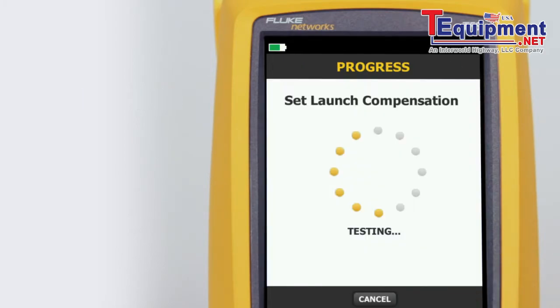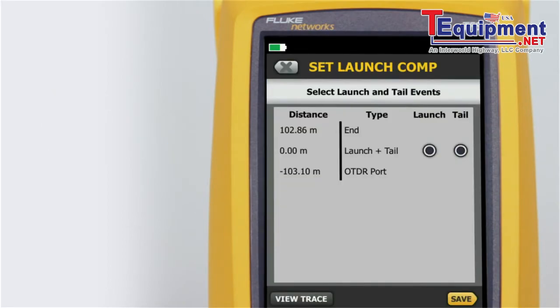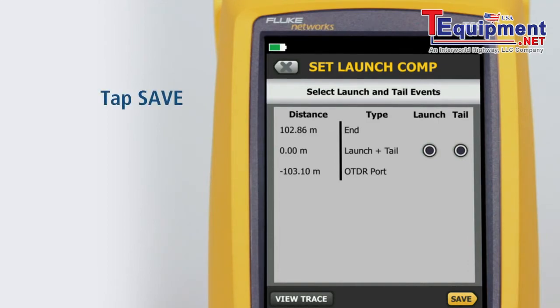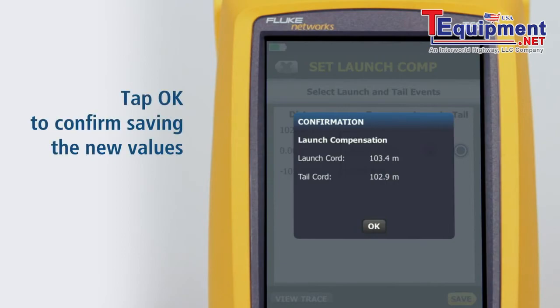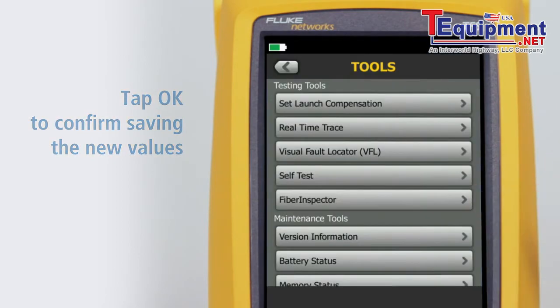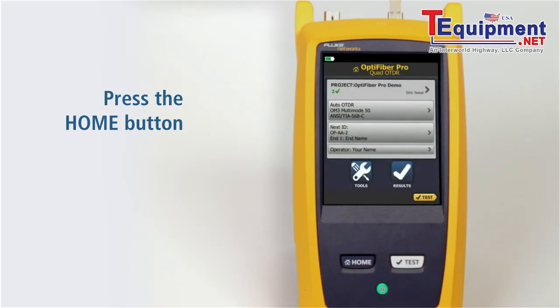The tester will analyze the launch and tail cord properties. Ensure that the port connection quality is good. The connection between the launch and tail cords is both the launch and tail event because we've connected the two cords together. Tap Save, then tap OK to confirm saving the new values. Press the Home button — we're ready to run a test.